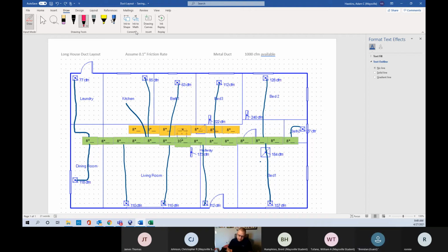All right, so go to 100 at 0.1, where most people would go, and they would say he needs a 6-inch duct. Here's what he did. Most rules will say as straight and as short as possible, because you don't want any bends that you don't need. You just want to run it straight there. Keep your equivalent length down.